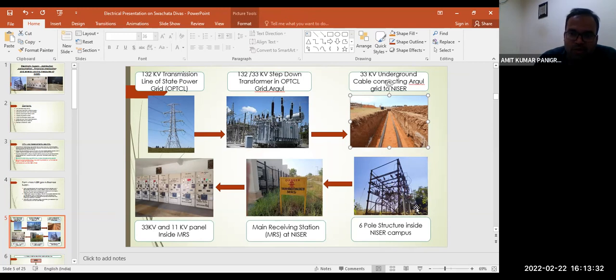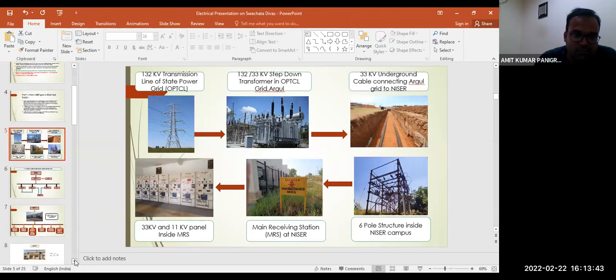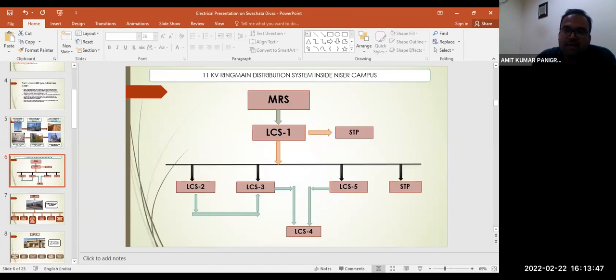From that 6-pole structure, our main receiving station is inside NISER. From the main receiving station, we distribute to different stations. In the main receiving station, we step down the voltage from 33 kV to 11 kV. At 11 kV, we have a ring main structure inside the NISER campus. We have different LCS, load control stations. We have 5 load control stations. The main one is LCS 1, which is near the School of Humanities. From LCS 1, we distribute to LCS 2, LCS 3, 4, 5, and another one, the STP. It is our 11 kV distribution structure.